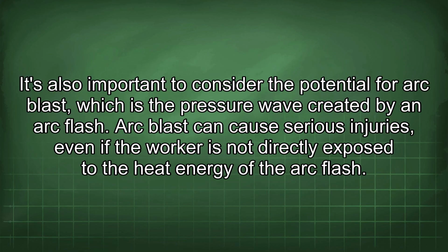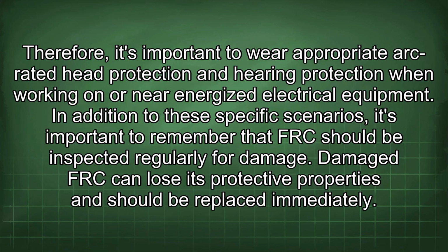It's also important to consider the potential for arc blast, which is the pressure wave created by an arc flash. Arc blast can cause serious injuries, even if the worker is not directly exposed to the heat energy of the arc flash. Therefore, it's important to wear appropriate arc-rated head protection and hearing protection when working on energized electrical equipment.